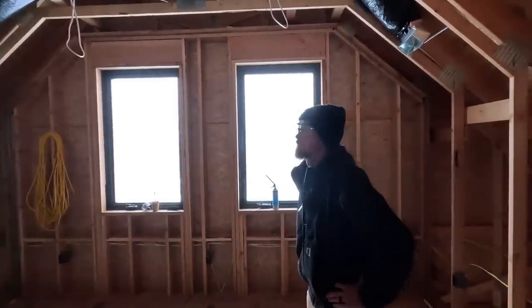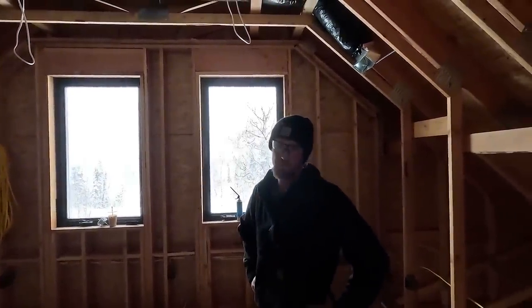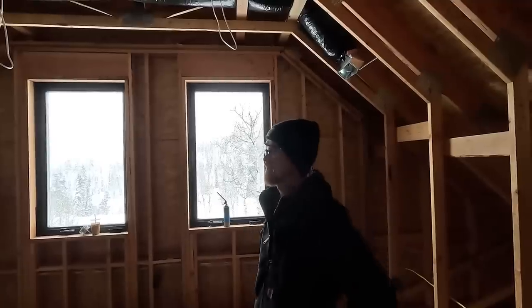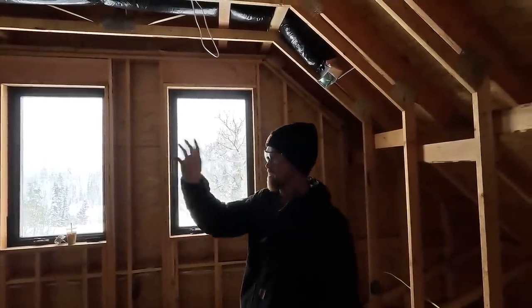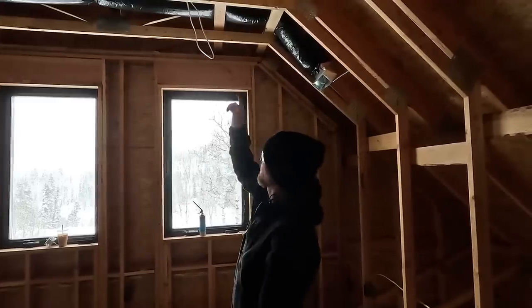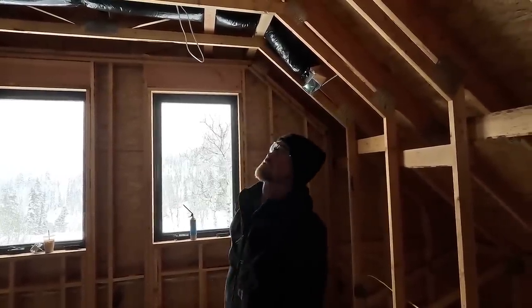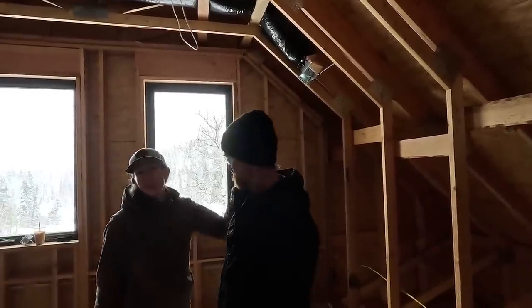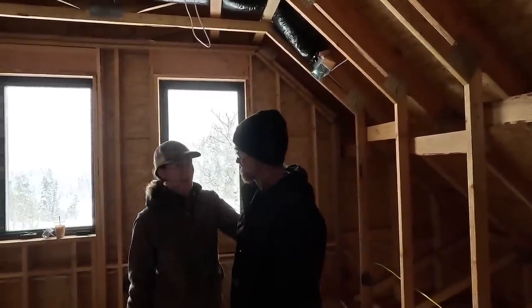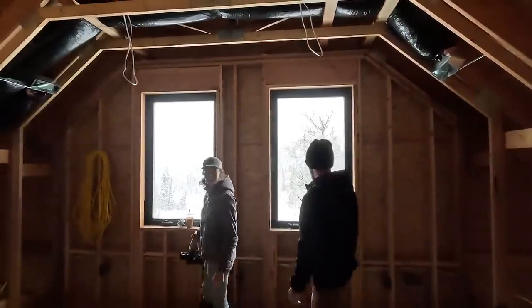Well, we're getting ready to replace the exhaust for the water heater because we used foam core PVC, and that is not allowed. You have to use solid PVC. So we got new PVC to do the exhaust for the water heater, and then we have to expand our vents for both of the drain, waste, and vent to 3-inch right before it goes out of the building. No better day to do some drilling into the side of our building than when it's snowing and freezing outside. Yes, exactly. It is a little frosty out there today.